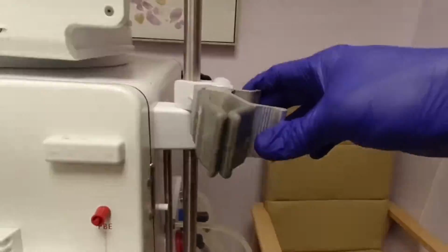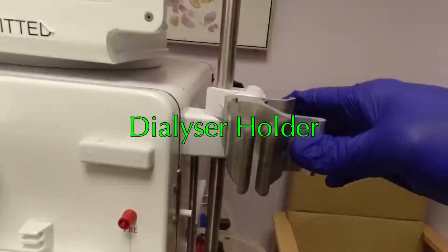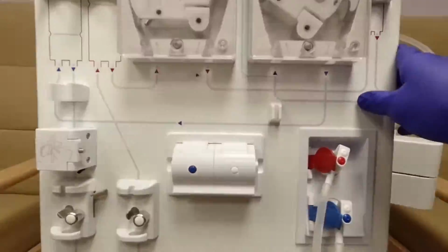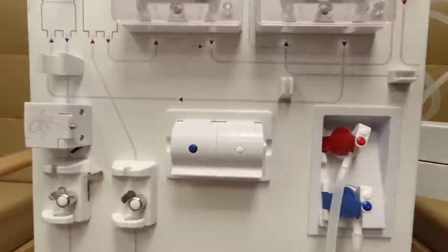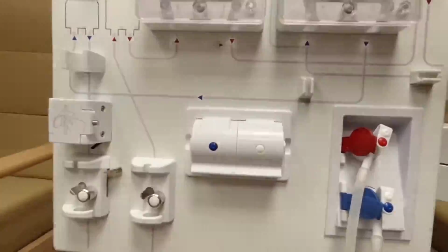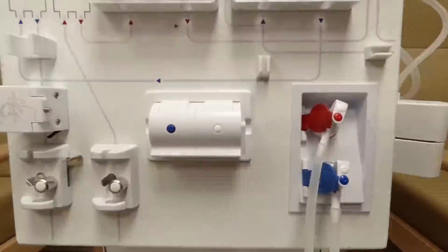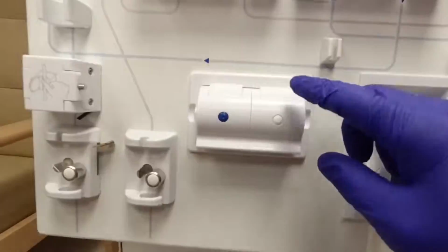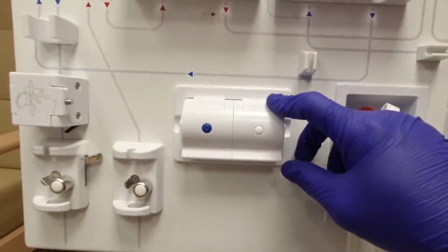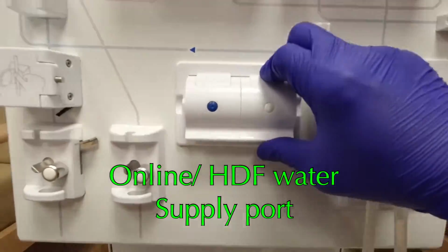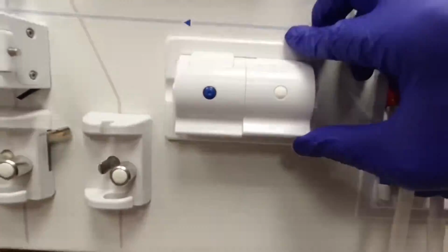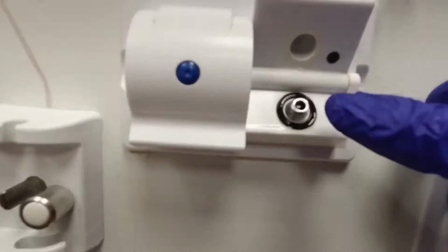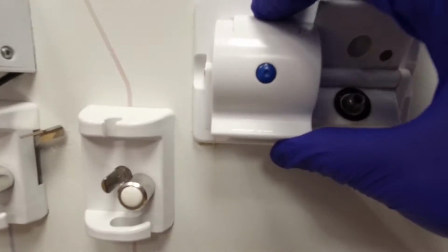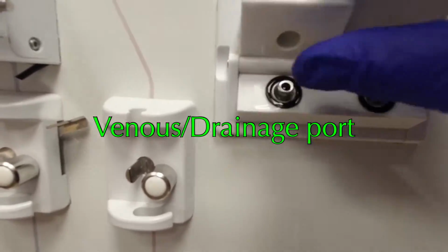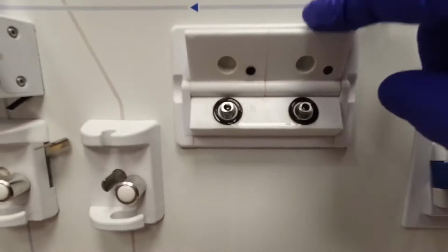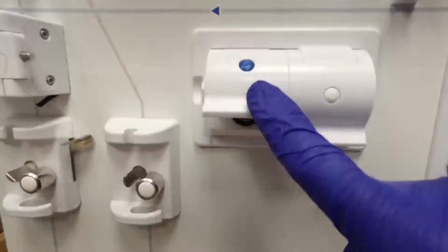All right, dialyzer holder, that's pretty straightforward. Since we're using a centralized water system, the reverse osmosis feed is on the back of the machine. We've got these two ports, one for online infusion. So you just click this on the top and then that will open in there. As you can see, there's a port in there, and same with the venous line. There you are. So it just snaps there in place to close it.